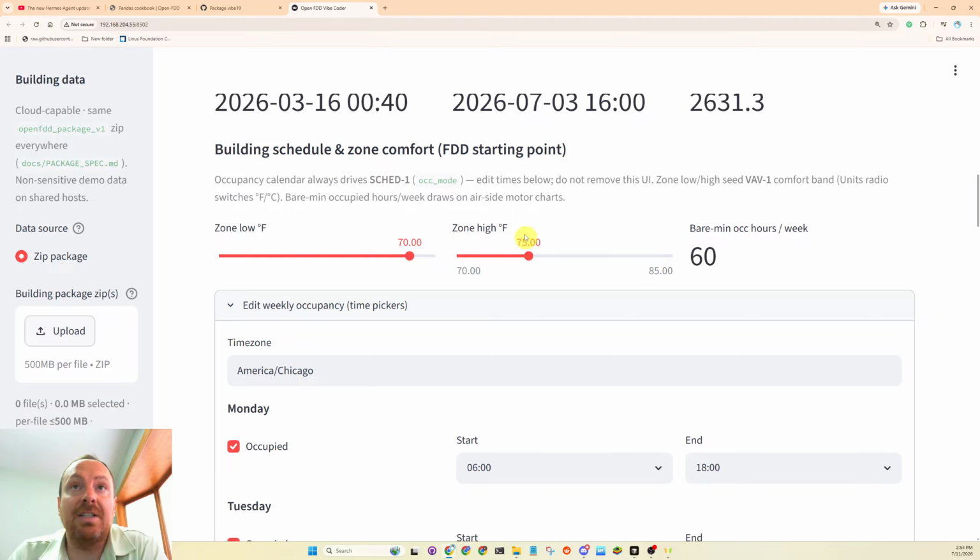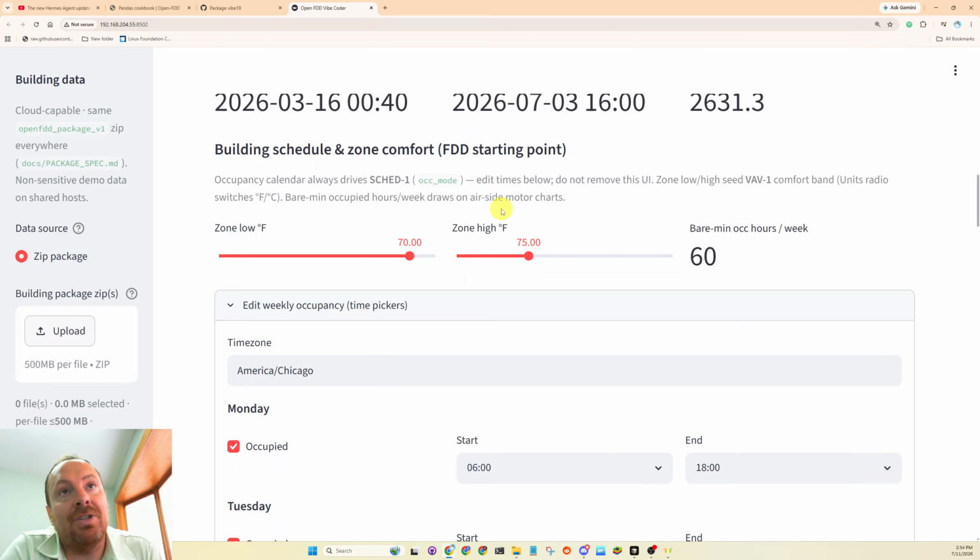In the United States, there's energy code requirements where they have a 5-degree deadband by energy code. The mechanical engineer always says the building needs to operate as code requires, because they're licensed to say how they want the building to operate, but no one ever automates it that way. I never realized that even existed until way later, 10 years into my building automation programming field technician work.